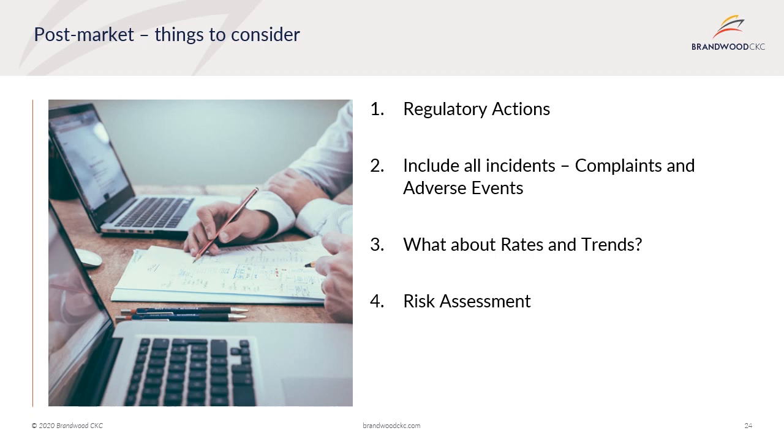This includes complaints and your adverse events. These should be clearly tabulated, with adverse events, especially those that are serious, discussed in detail. This includes discussion on whether or not they are device related. Include as much detail as possible: the types of events that occurred, the geographical locations, and whether or not there was a patient impact.